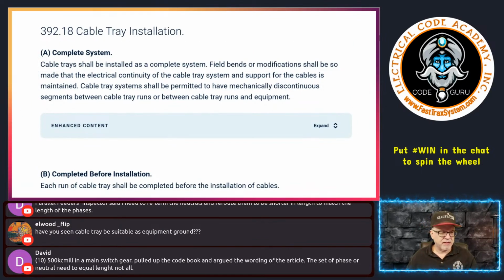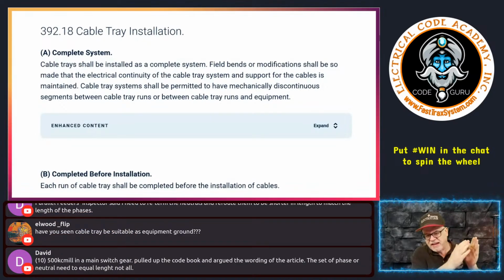Let's see here. What is this? Oh, let me get back to comments here. What did David say? 10 500s in the main switchgear. Pull the code book out. Argue the wording of the article. The set of phases and neutral need to be equal length, not all. Yep, just all the neutrals need to be the same. All phase A need to be the same. All phase B need to be the same. All phase C need to be the same. They don't all need to be the same with each other, okay? Because it's all about the distribution of current.